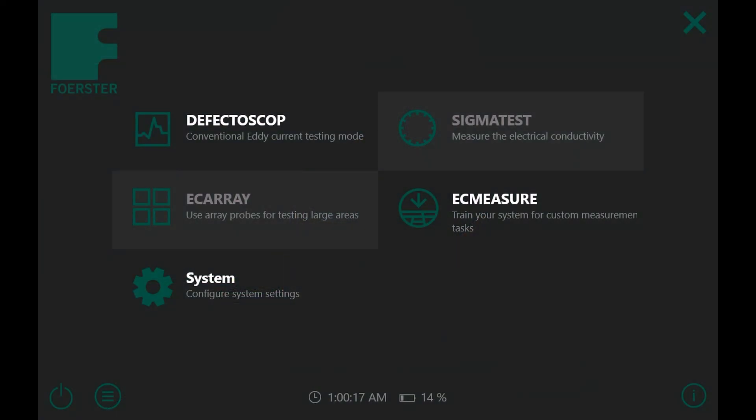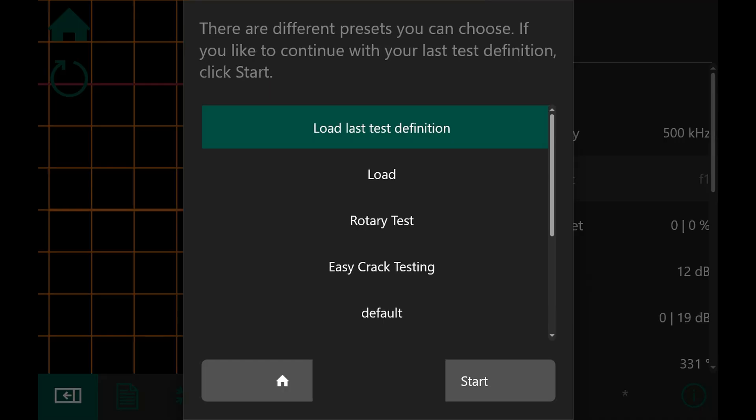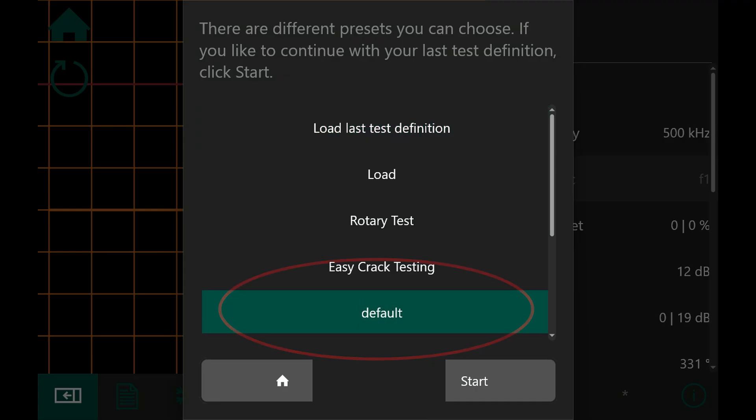The DEFECTOSCOP app is the standard program for conventional eddy current testing and mainly used for applications like surface crack testing, borehole inspection with rotating probes and residual wall inspection. To open the DEFECTOSCOP program, tap on the icon. An overview of presets appears. I select the default preset.